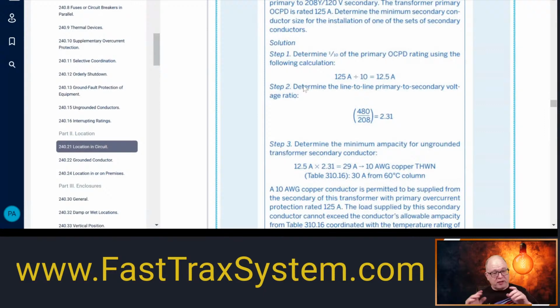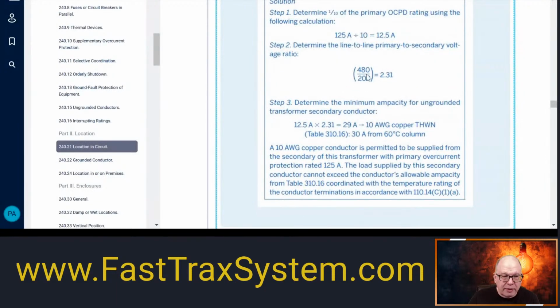All right, so solution. First thing we need to do, remember what it said? Field installation. It's got to be at least what? So first we want to find 1/10 of the overcurrent protective device that's protecting the primary. We said it was 125 amps, so 125 amps divided by 10 is 12.5 amps. To determine the ratio, remember what we said earlier? We take the primary and divide it into the secondary, and that gives you 2.31. It's actually 2.307, which rounds up to 2.31. So 12.5 times 2.31 equals 29 amps. In this case, it would be a minimum of 10 copper.